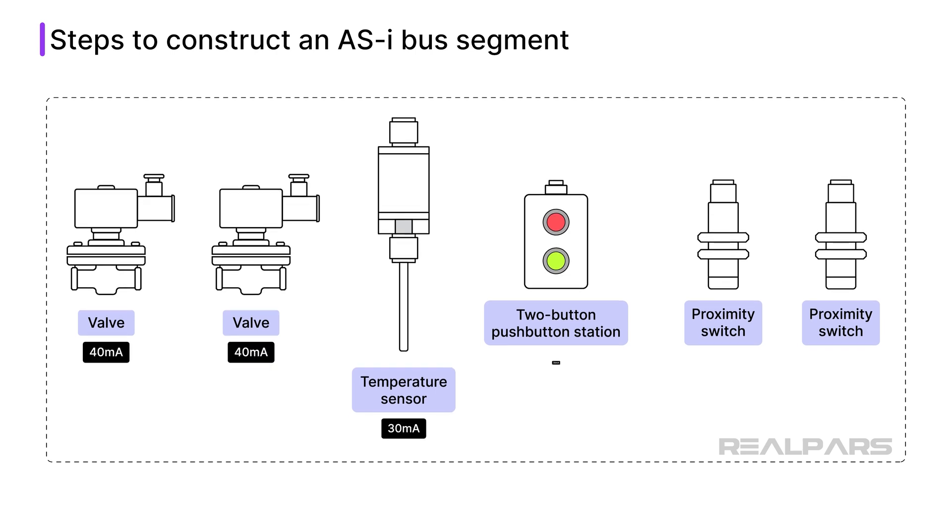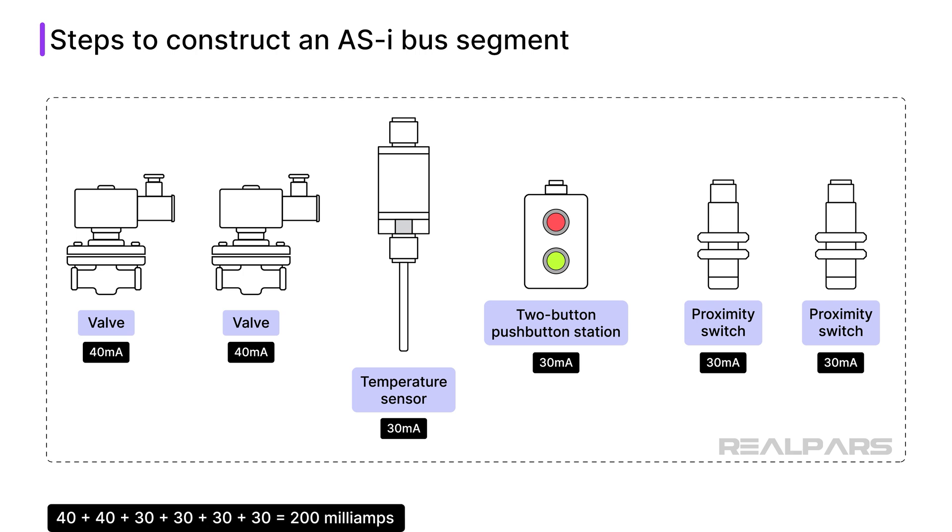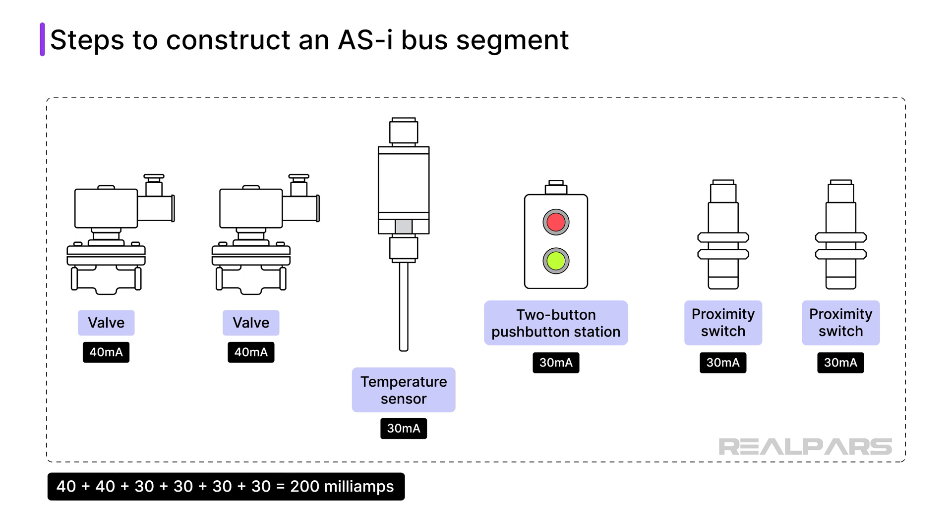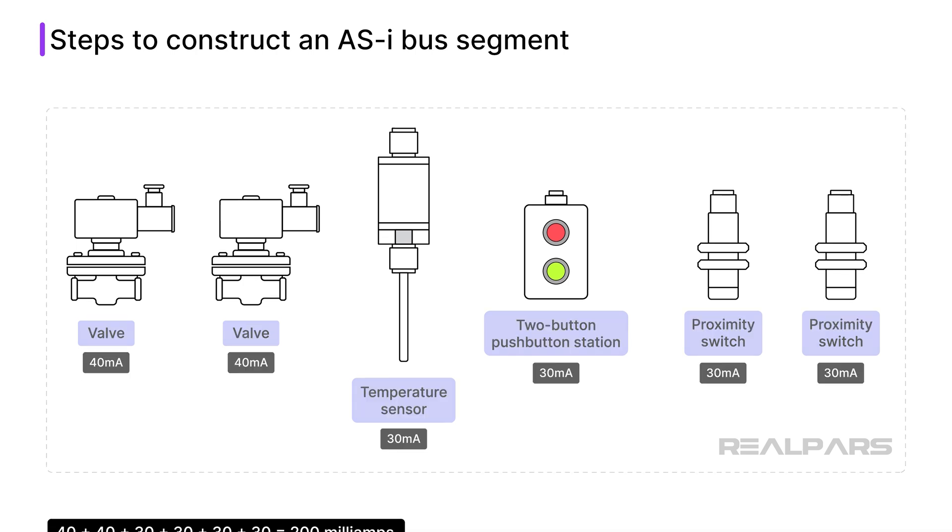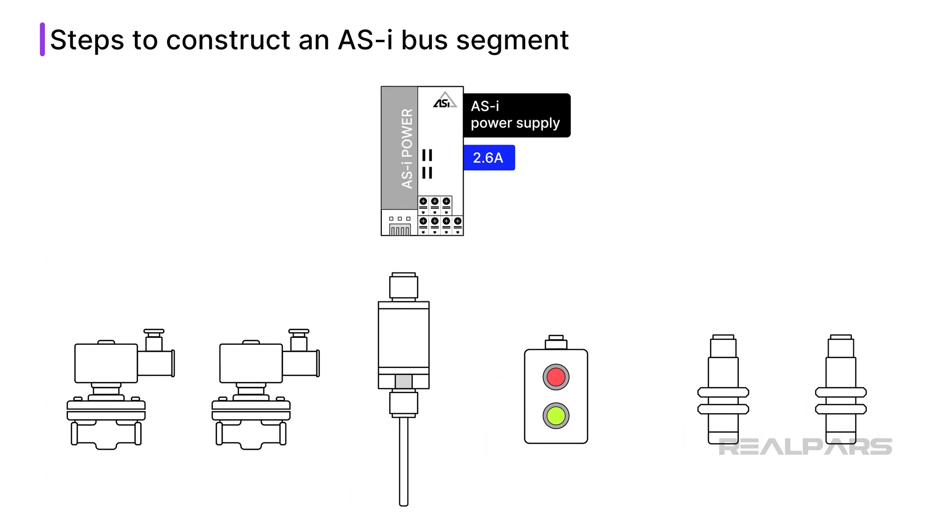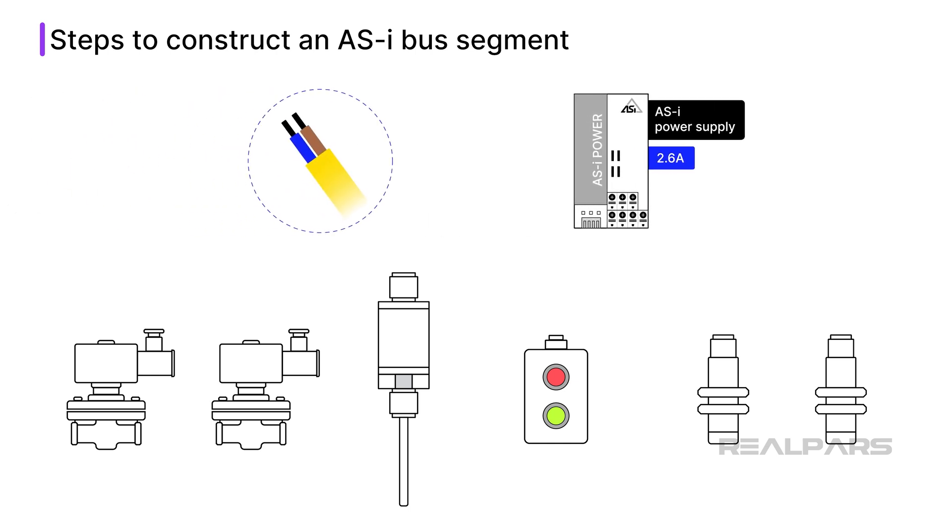I have determined from the device manufacturer's data sheets that I will need 40 milliamps for each valve, and 30 milliamps for the other four devices. This means my power supply will need to provide at least 200 milliamps, a very small amount. A 2.6 amp power supply will provide more than enough power for my segment. I choose to use standard round cable to install my segment.